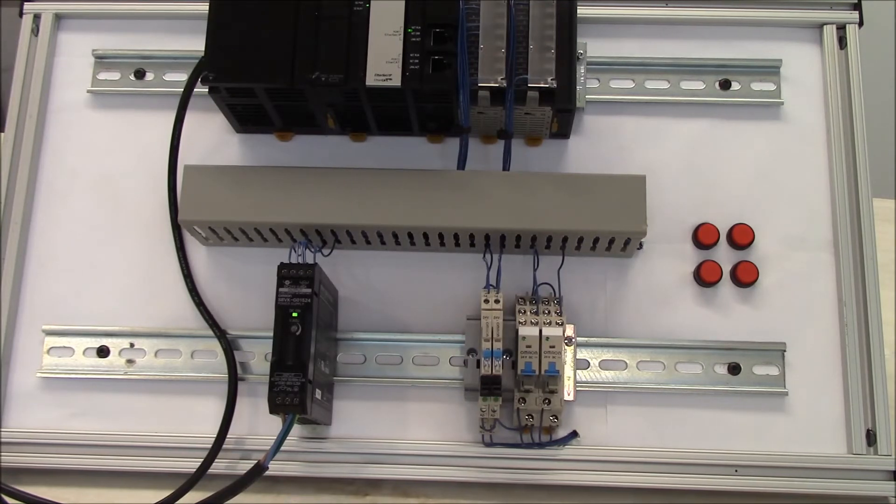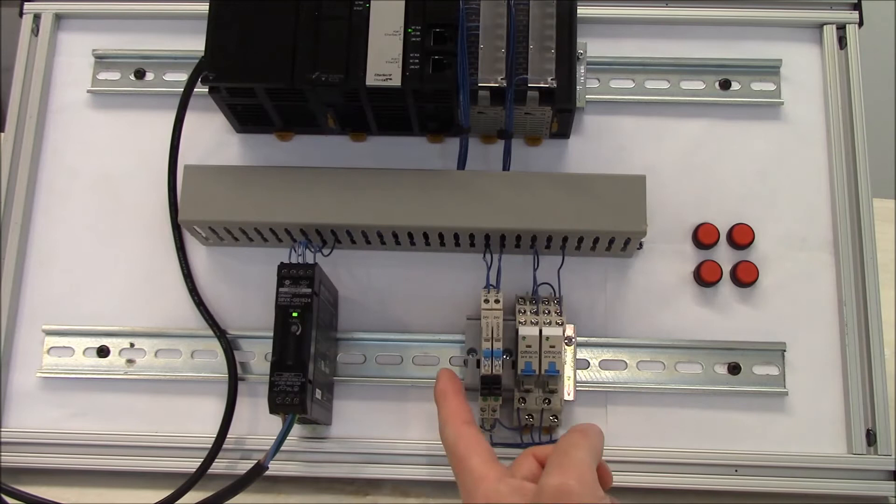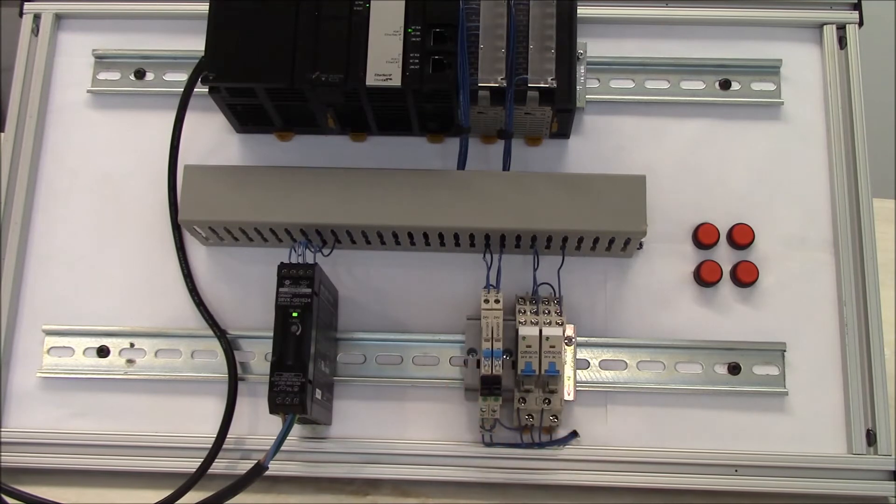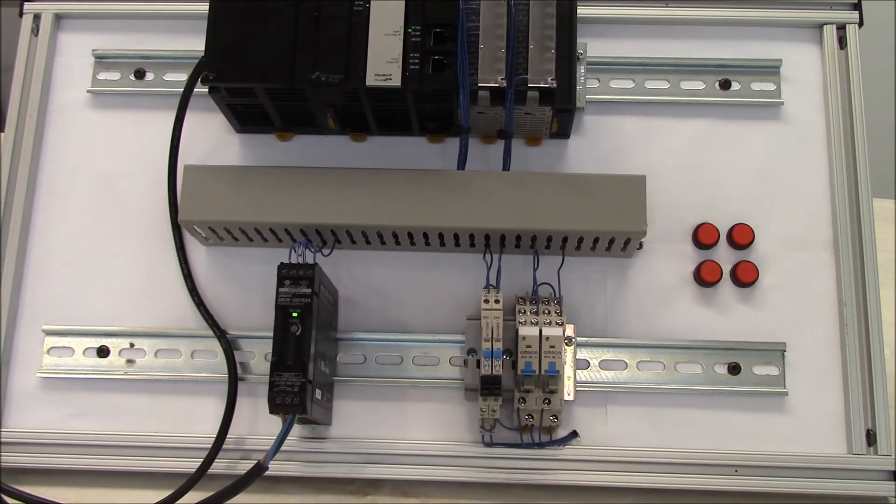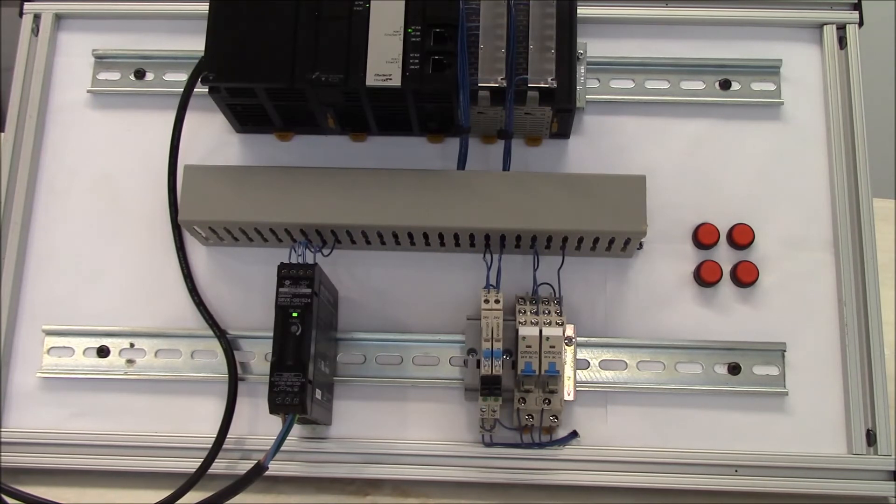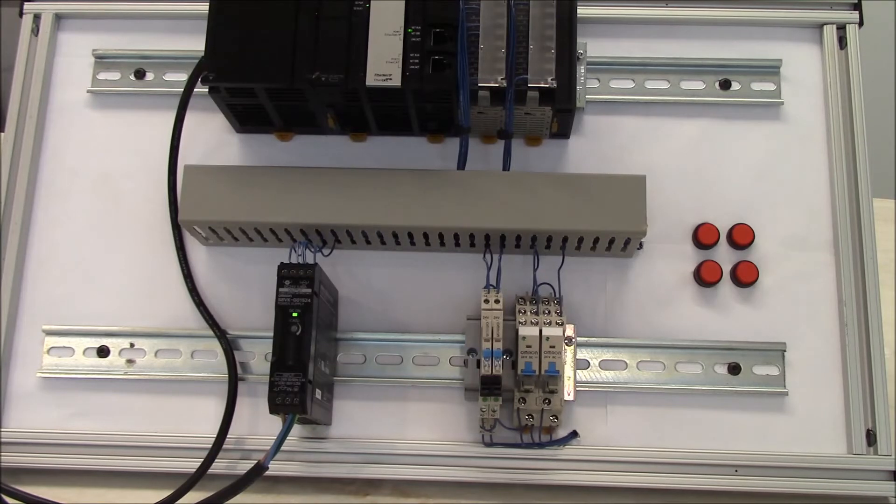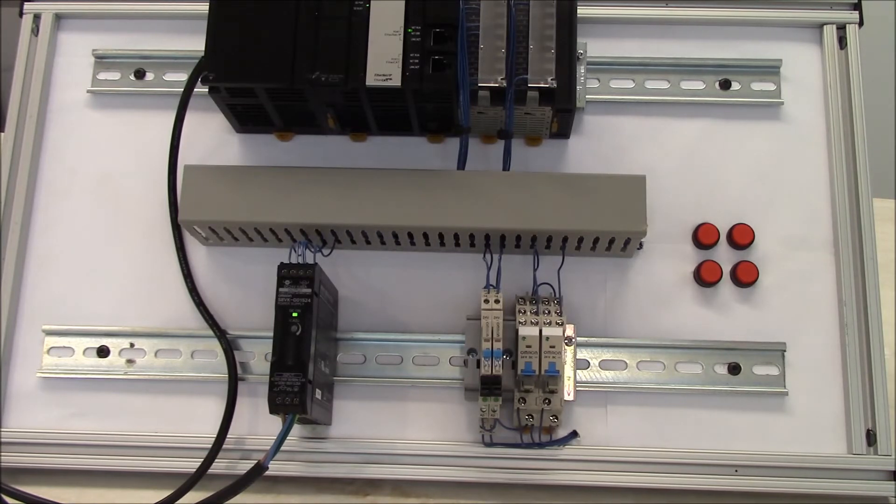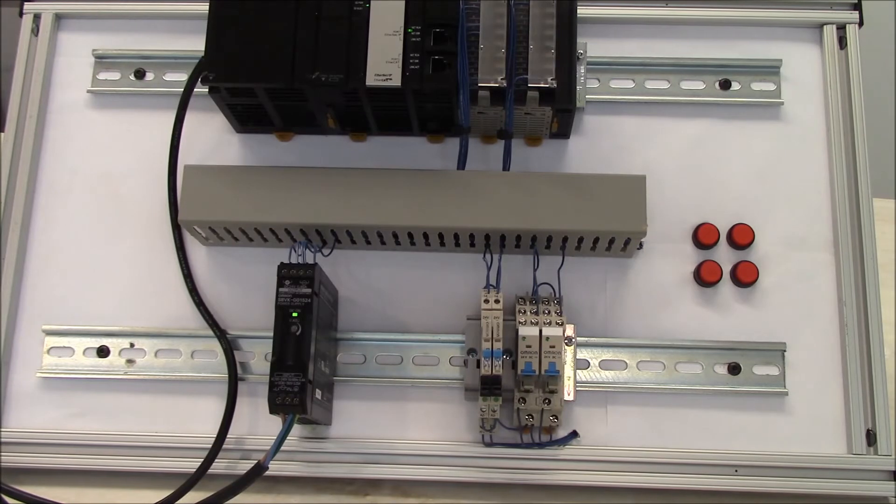The package itself comes in 6.2 millimeter wide to save space. We do offer a 6-amp contact rating on that, and you can get anywhere between 100,000 to 200,000 electrical operations depending on the current you're running through the contact.